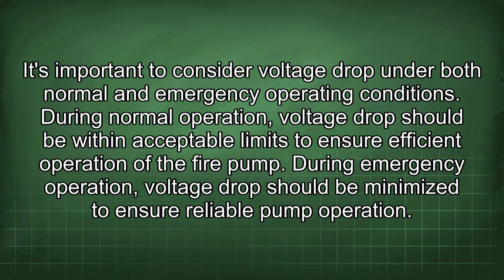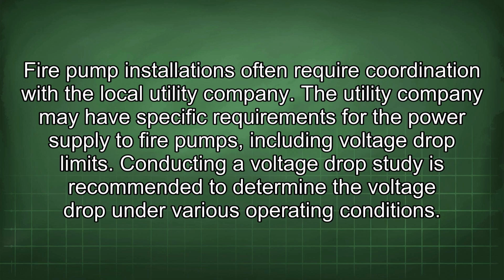It's important to consider voltage drop under both normal and emergency operating conditions. During normal operation, voltage drop should be within acceptable limits to ensure efficient operation of the fire pump. During emergency operation, voltage drop should be minimized to ensure reliable pump operation. Fire pump installations often require coordination with the local utility company. The utility company may have specific requirements for the power supplied to fire pumps, including voltage drop limits.